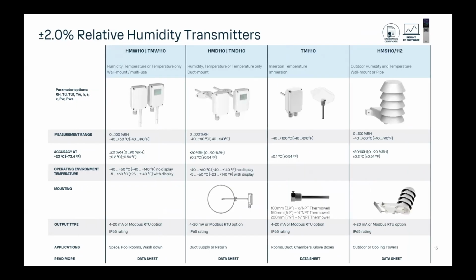So continuing down the line, we have our plus or minus 2% humidity sensors. So these are still no remote probe, but we have the option for wall mount and also for duct mount. Still the humicap sensor, still traceable calibration certificates. Here you'll see that we actually have a specific model all the way on the right for outdoor measurement. So this features the radiation shield, and I will touch on this later, but the radiation shield actually has a specific design that allows airflow in, reflects sun and elements away, but then the bottom, you'll see on this bottom right picture, is painted black. The reason for that is so sun gets absorbed and not reflected up and heats up that space and creates a bit of a microclimate that would mess with the measurements.